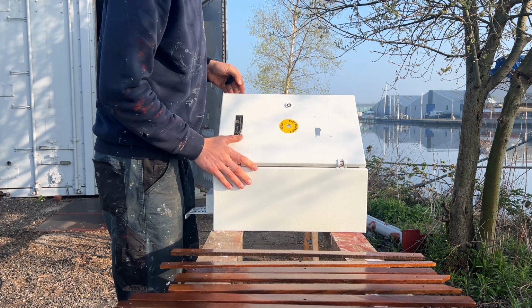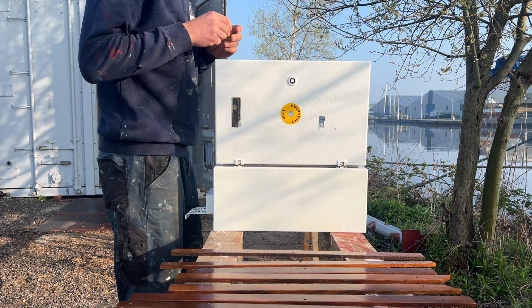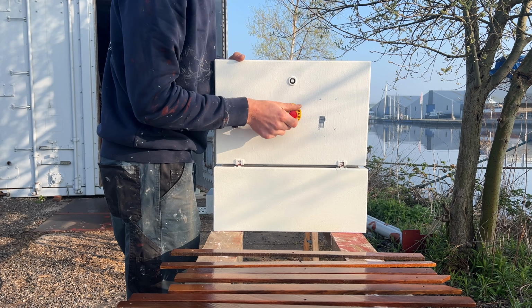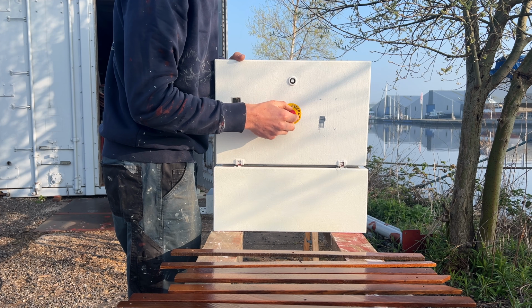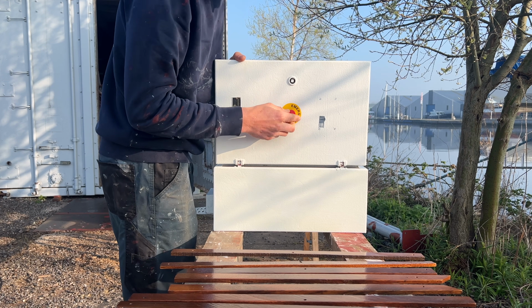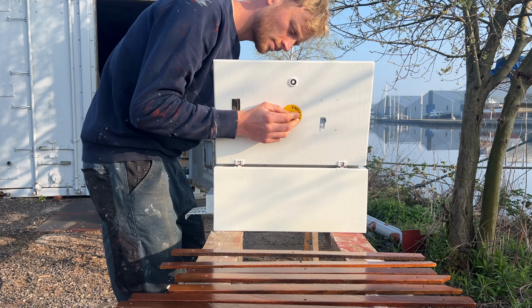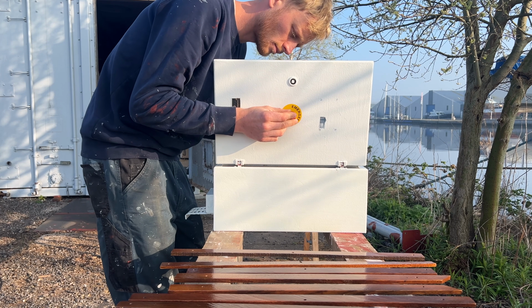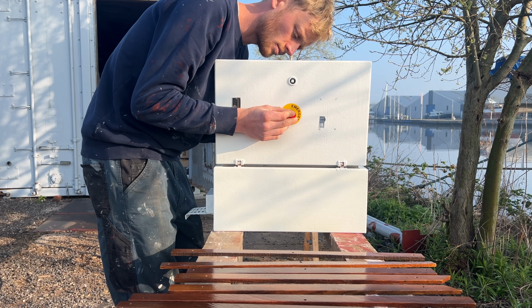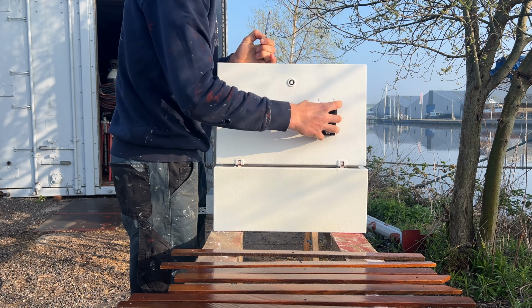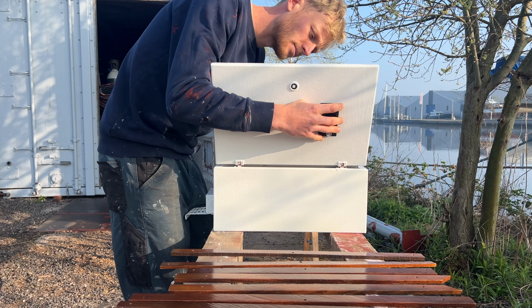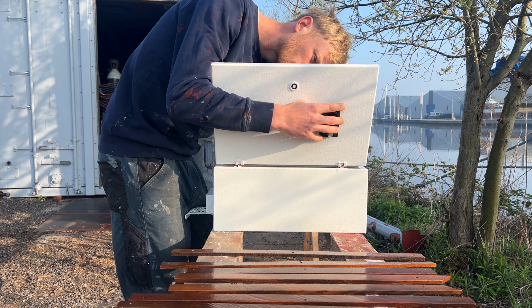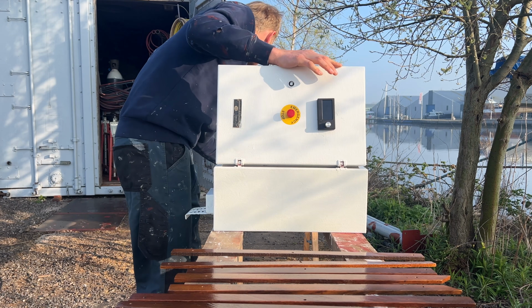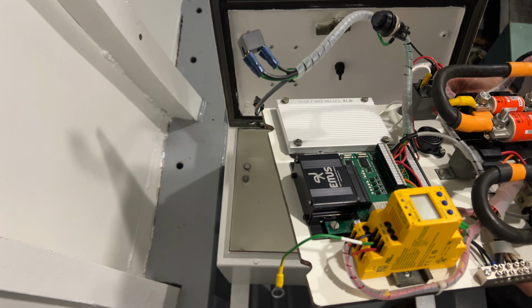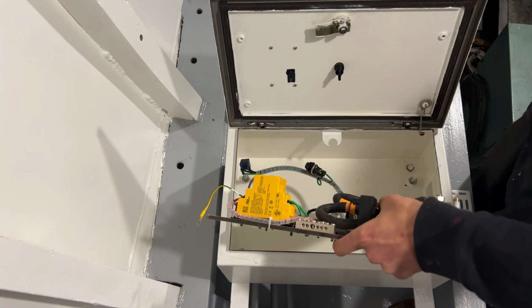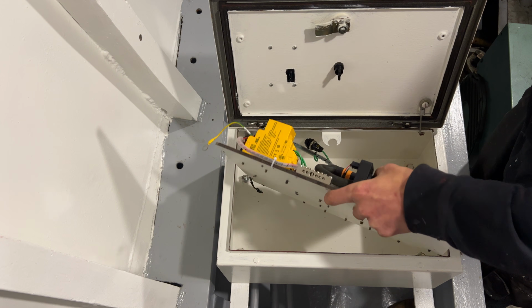On the outside of the door there's an emergency stop switch. It does the same thing as the door interlock, but it's also wired directly into the control line of the contactors. So even if the BMS were to fail, the emergency stop will always open the contactors. And finally, there's a display on the door, so we can monitor everything without opening the cabinet. And the BMS also feeds data to our navigational displays, so we can keep an eye on the battery from the wheelhouse, and even from the aft deck.